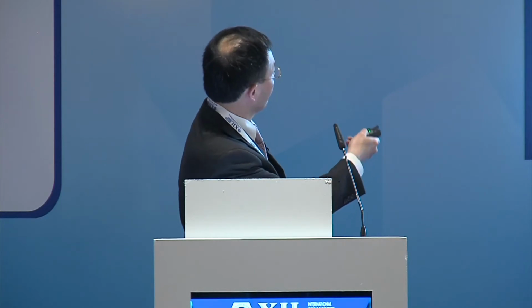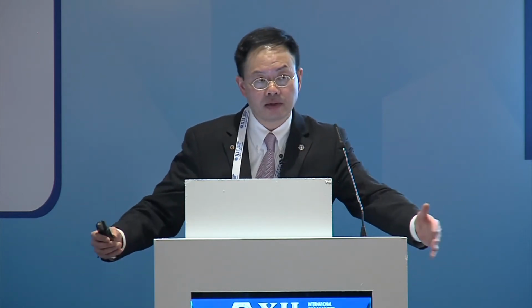The ASHRAE 170 standard requires a minimum of 1 foot around the patient bed, and you can add additional filtered supply air surrounding the surgical bed. But as the USA ISO representative, personally I have had lots of interface discussions with European counterparts on their healthcare operating room and isolation room design standards and practice. The major difference between the US and the European countries, and I'm not talking about one or two, but multiple countries: in the US, we're still very conservative, only 1 foot wider on both sides of the patient bed for the HEPA filter coverage.